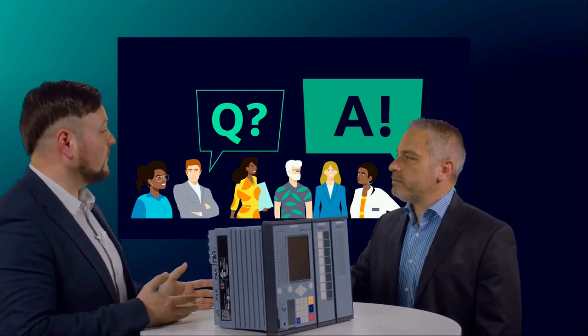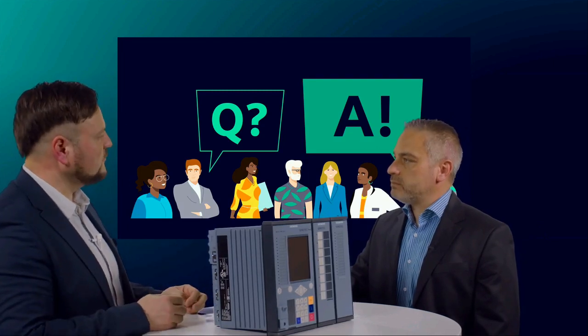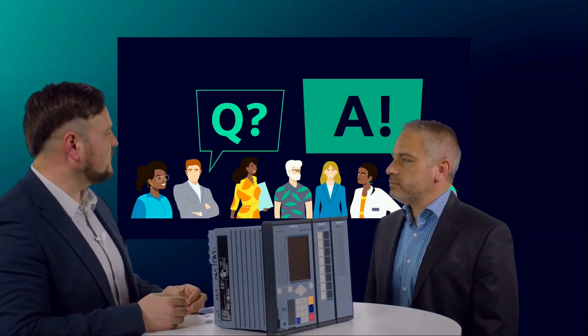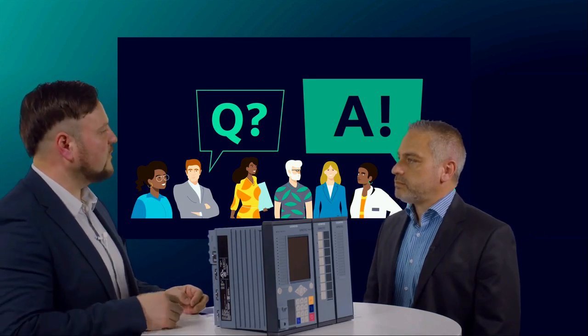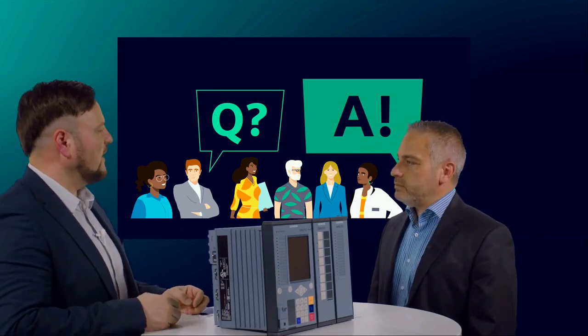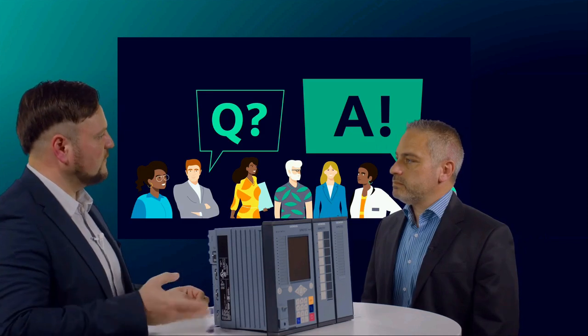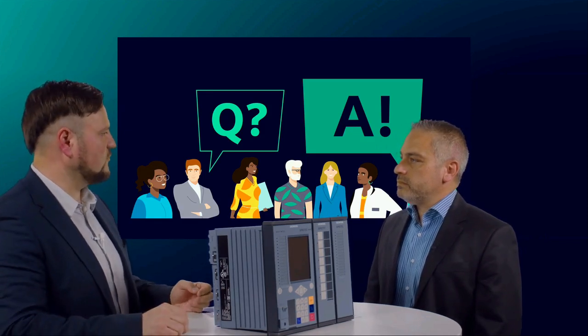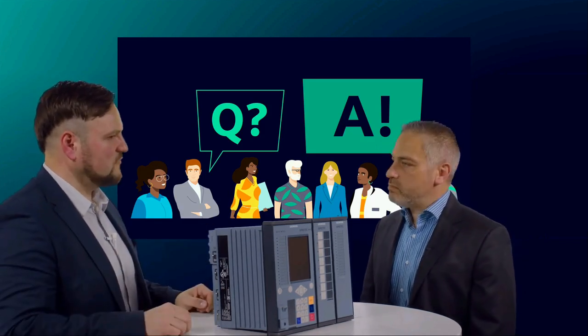This can be used for synchronous motors, asynchronous motors, and also if you have generators connected on the motor bus, we can handle that too, because in a transfer you have to disconnect the generator first, and afterwards reconnect or resynchronize it to the motor bus. So there is no restriction.